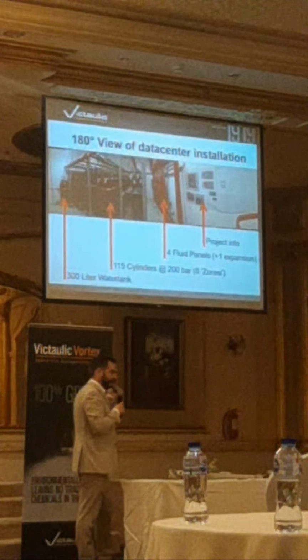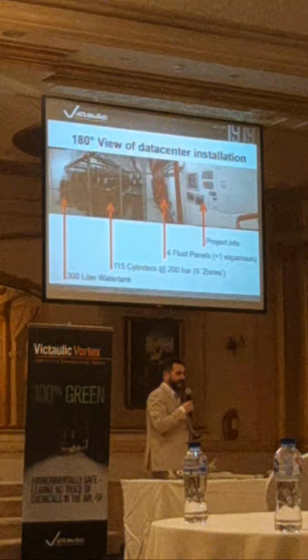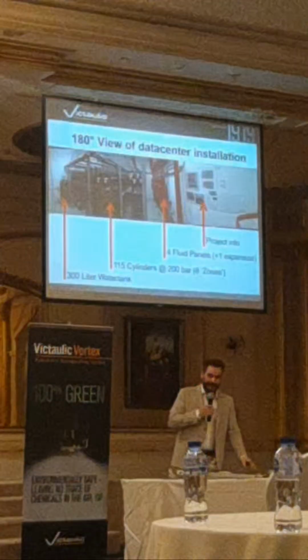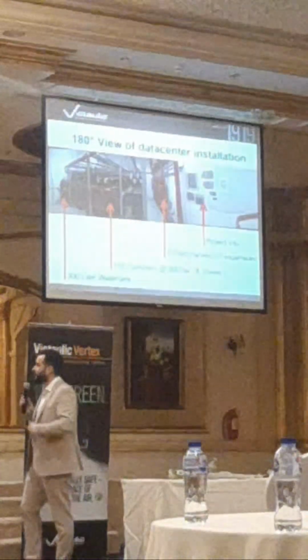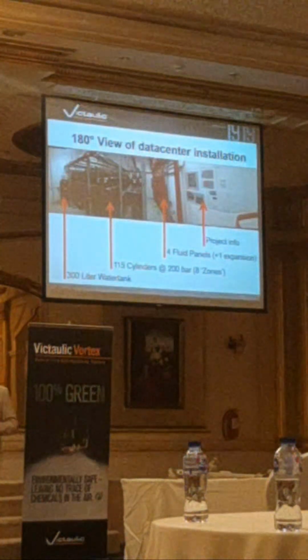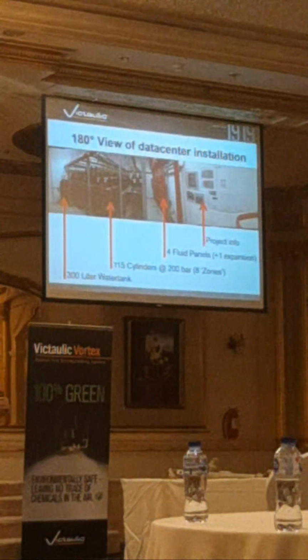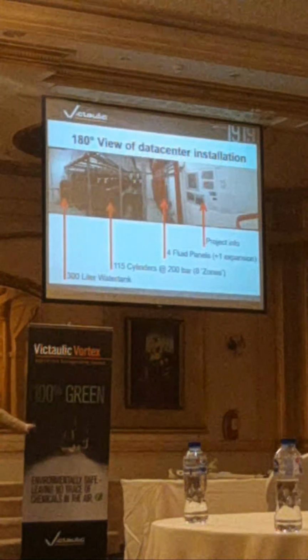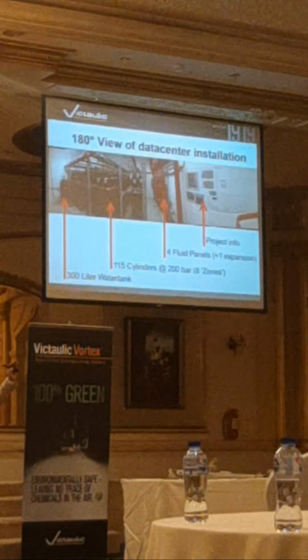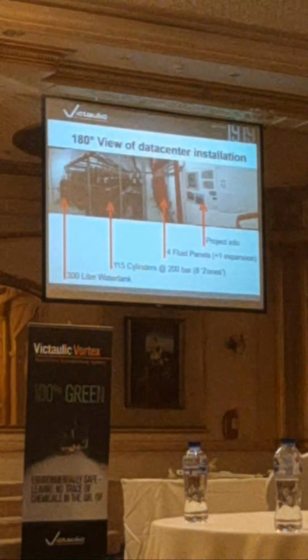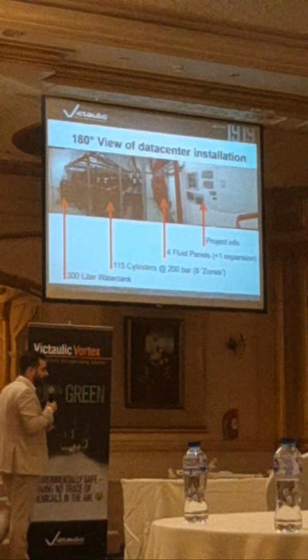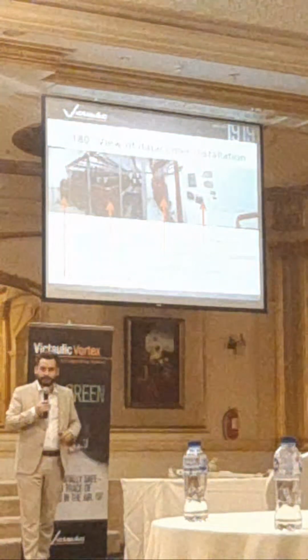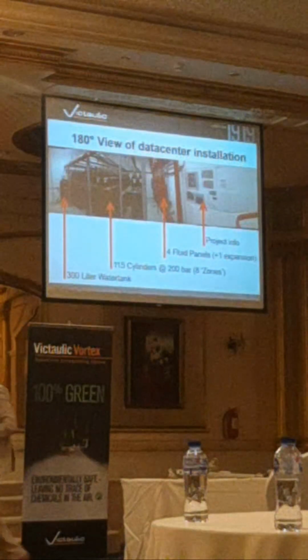And the amount of cylinders that we needed are also, it's only the one system. Because you have the low pressure line, this was protecting 150 meters of a building, 50 meters wide, and 2 floors up. Electrical rooms, battery rooms, data halls, switchgear rooms, low voltage was also protected by this single installation.